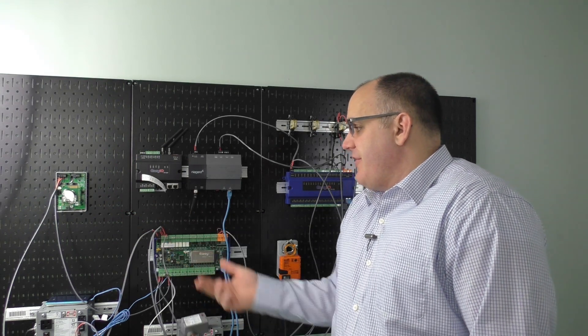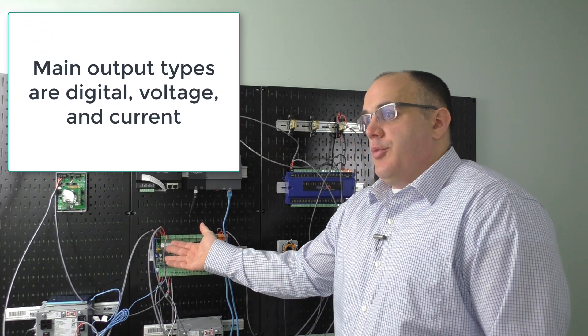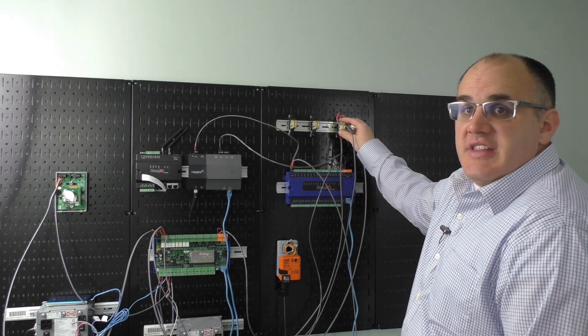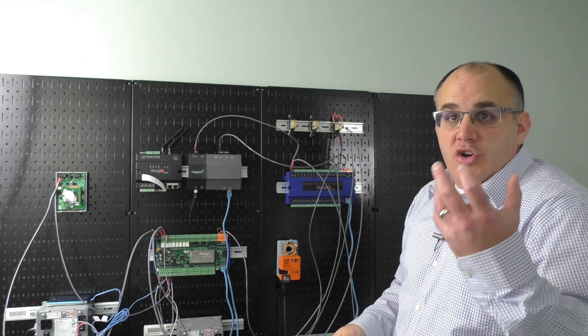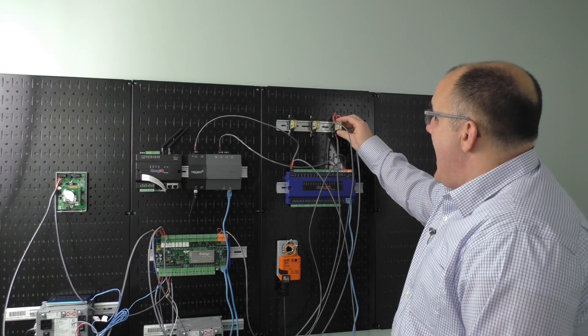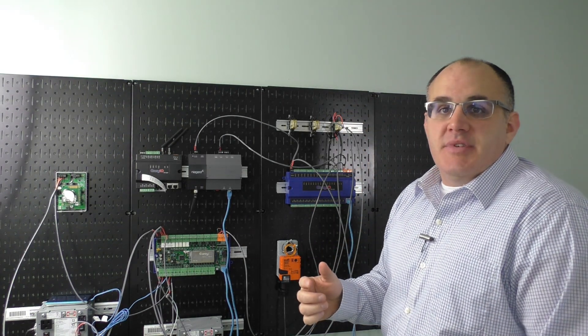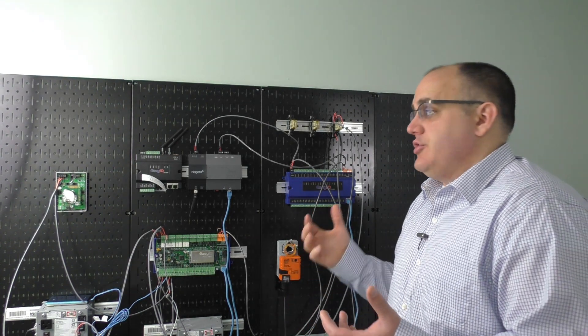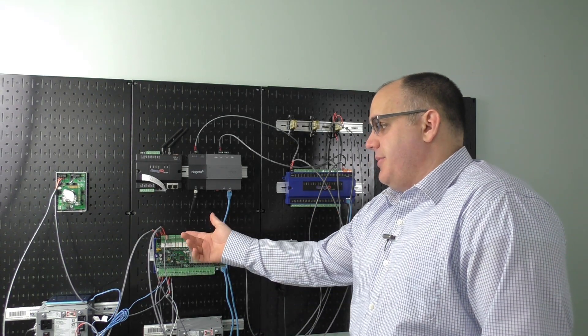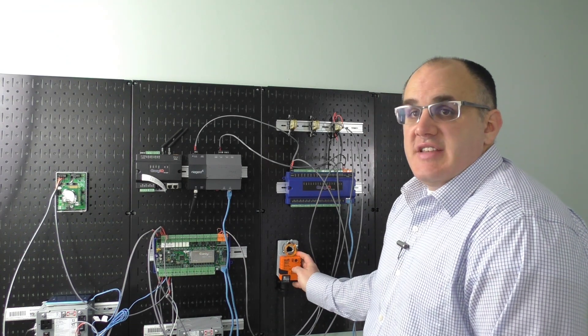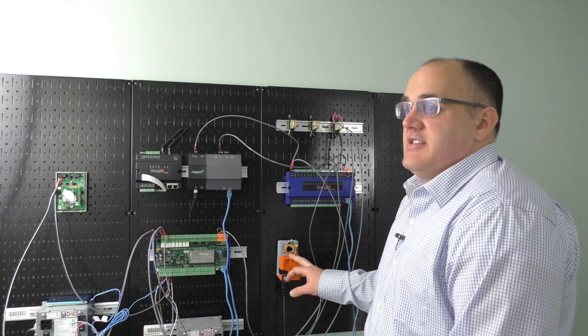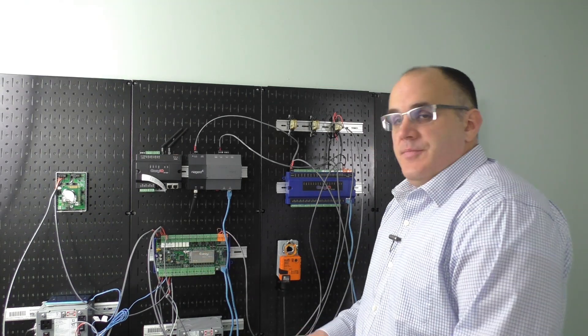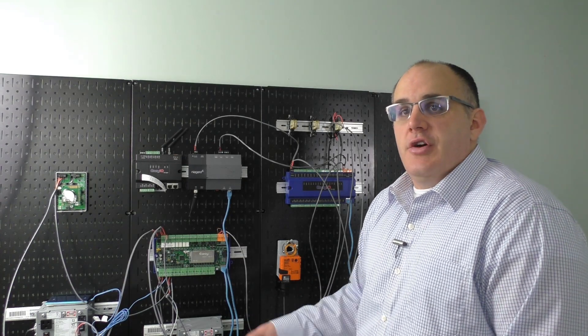As far as outputs go, we have a variety of different output types. We have digital outputs where we can provide voltage to drive a relay like these IDECs up here. These are single pole double throw, meaning you have a single coil and two contact positions, also known as throws. When you energize that coil, the contact position is going to change state. The normally open will go to closed, and the normally closed will go to open. We also have voltage outputs that we can drive, like 4 to 20 milliamp or 0 to 10 volts for this actuator.